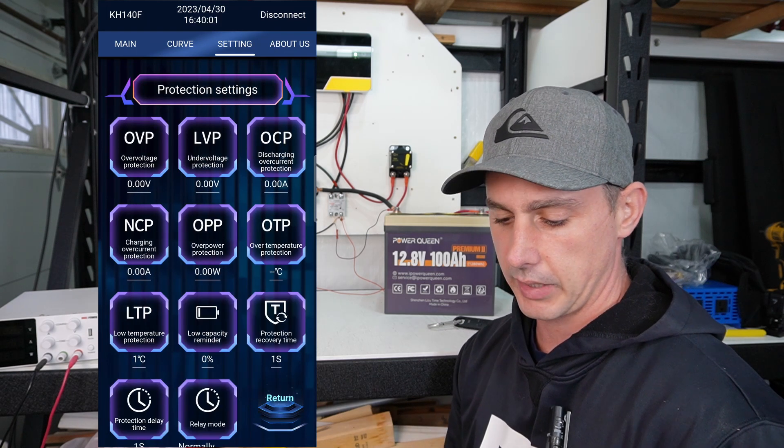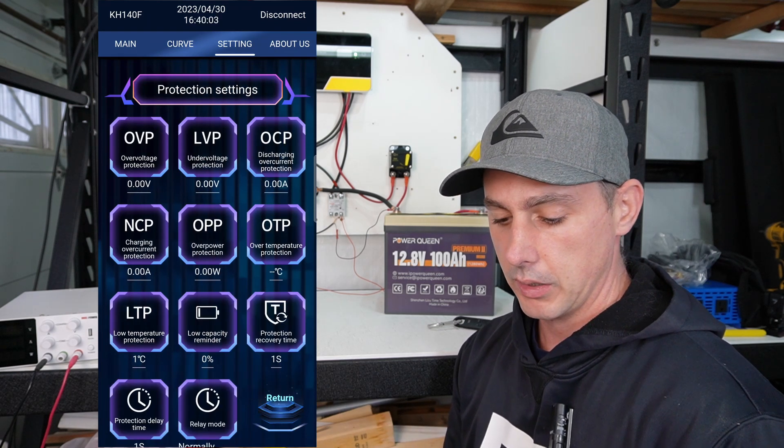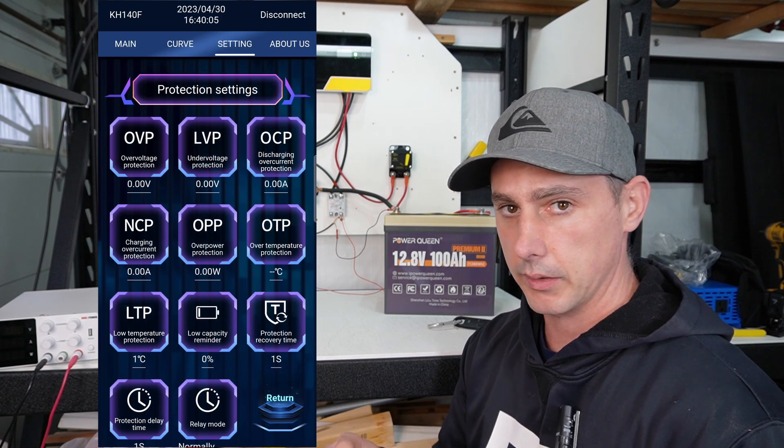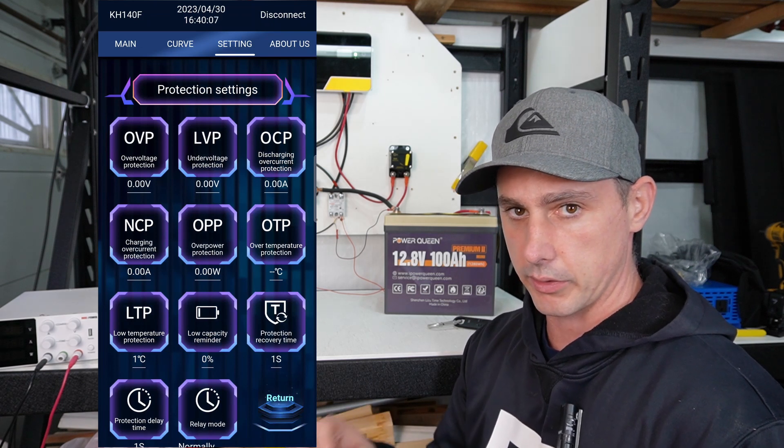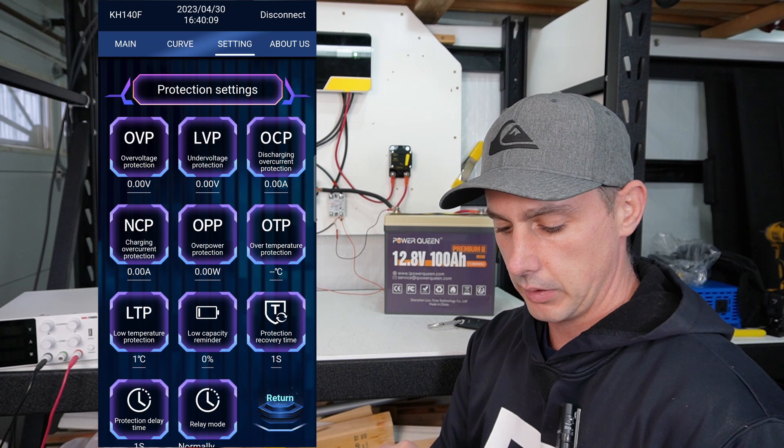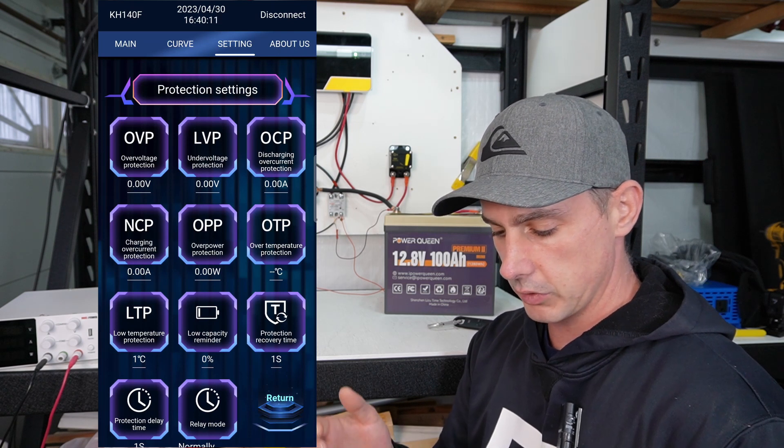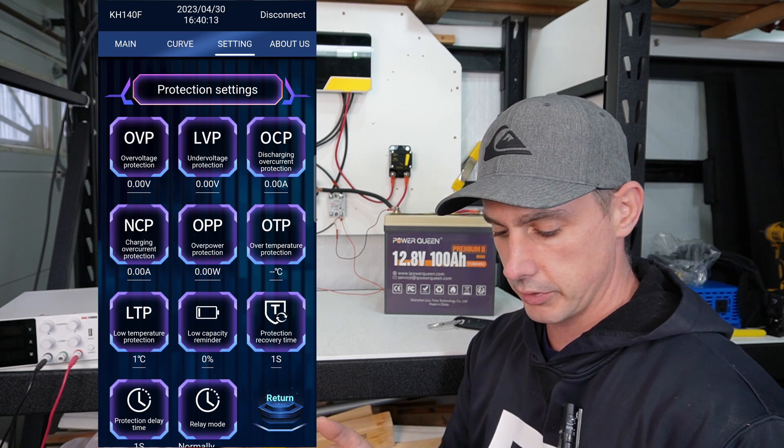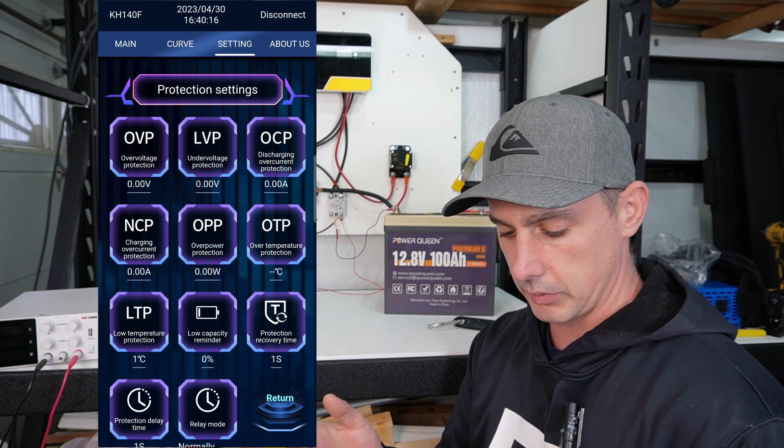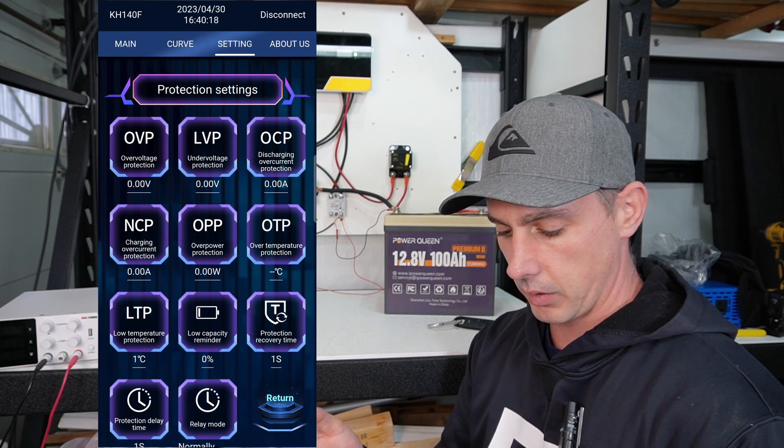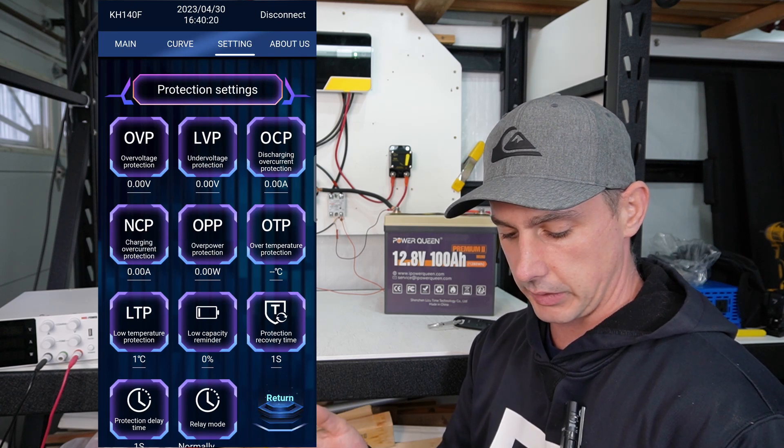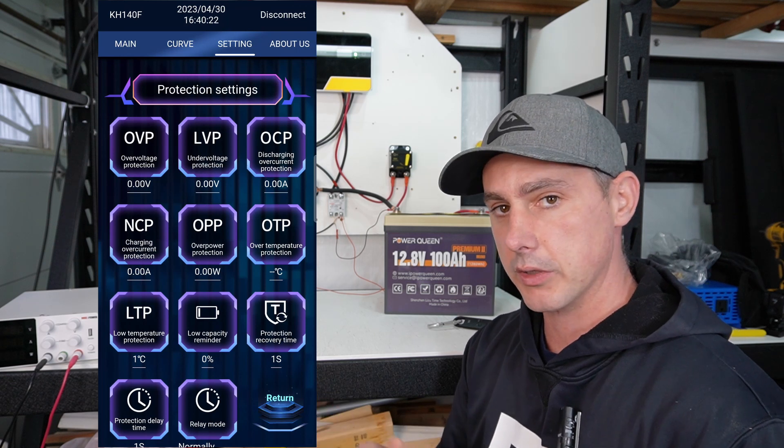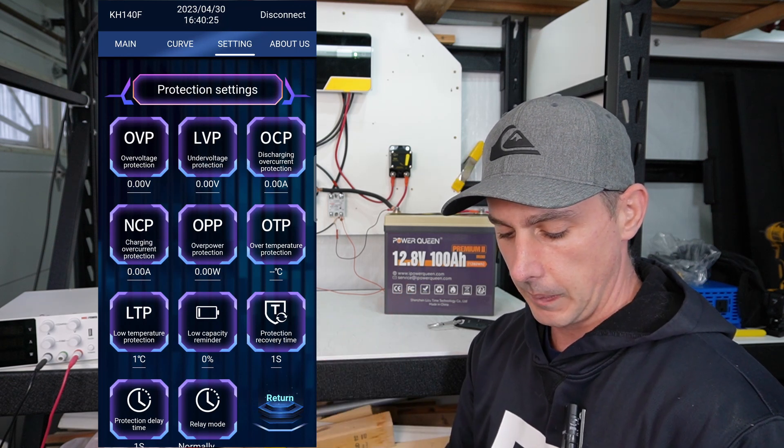So now setting protections. This is really cool. So you can set up a relay to trigger during certain events. So you can have over voltage protection, under voltage protection, discharge current protection, charging over current protection, over power protection, over temperature protection, low temperature protection, which I have this wired up for that right now.